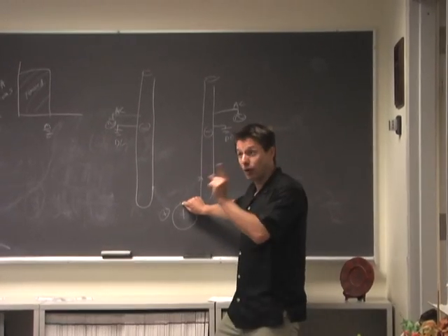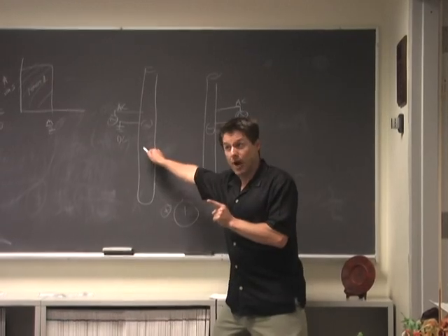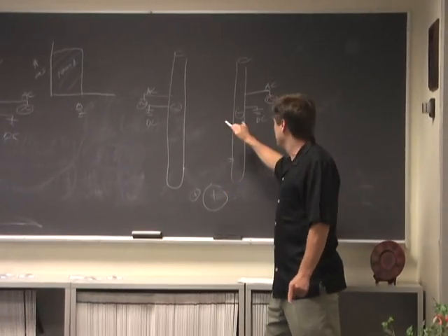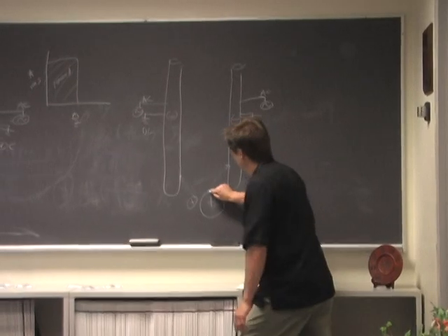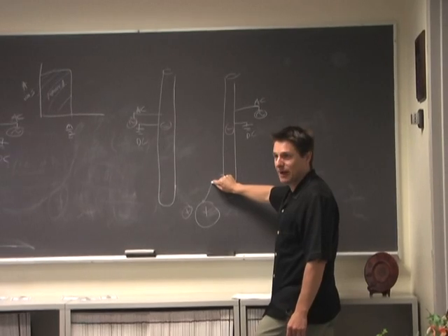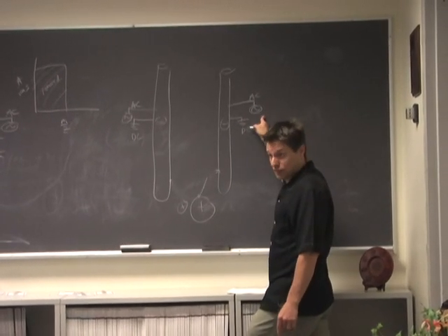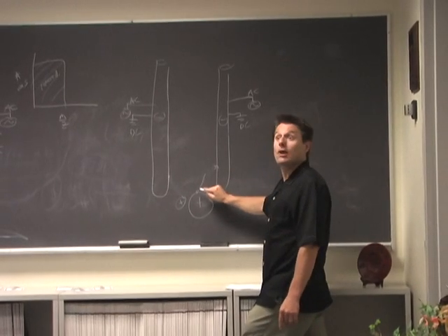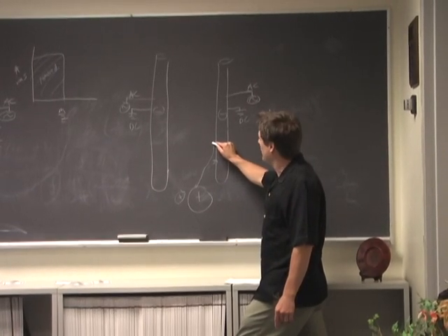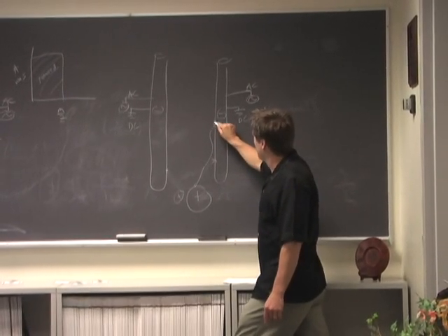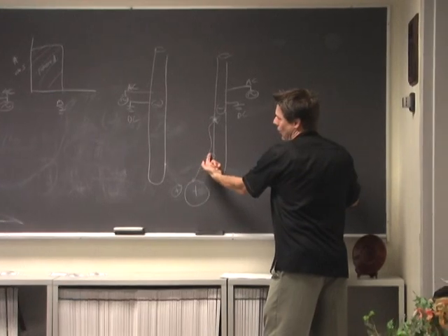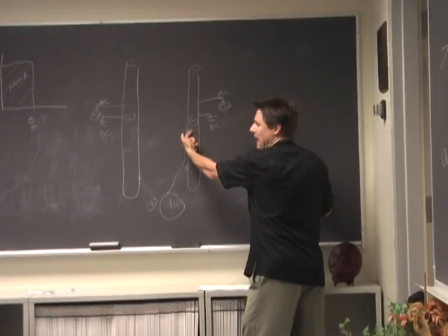Let's take the big one — it can't turn its path very fast. Its general path is towards the rod. Because they're negative, it wants to move towards the rods at all times until they turn positive. The alternating current goes negative, and you've got a big massive titanic moving in this direction — hard to turn. Now the AC turns positive and overwhelms that. The ion tries to turn about, but then it's negative again, then positive, and it crashes and burns. The big ones get taken out.